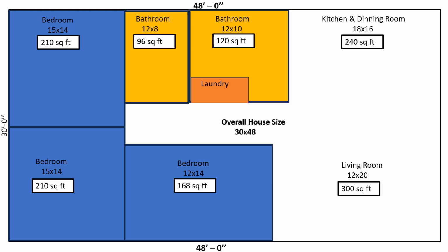So this was the math formula that I was given 28 years ago, 27 years ago. And he said, this is how you actually do it. You take your square footage and you multiply by this, and you get this 0.72 or 73 number. And you take that number and you multiply it by the square footage of each room. And that's how many CFMs that room needs to heat and cool. This is based off of 8-foot ceilings, normal 3-foot by 3-foot bedroom window. Now, of course, if you have a wall full of glass or a storefront or higher ceilings, you really need to get a Manual J.